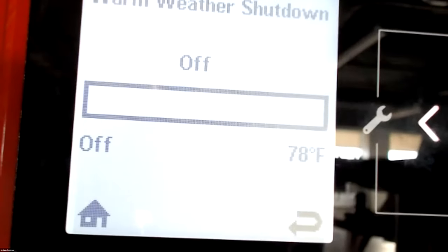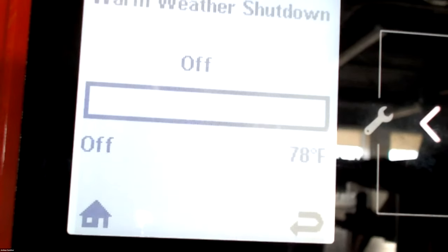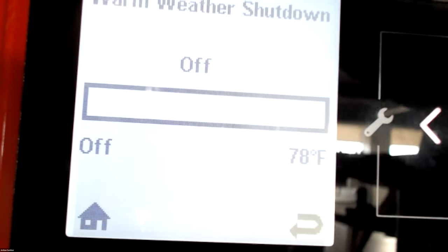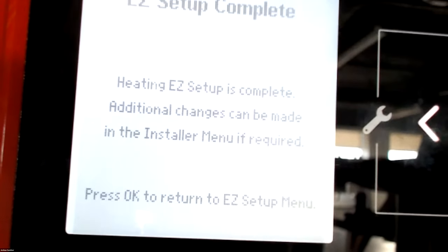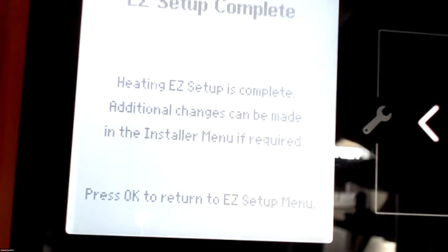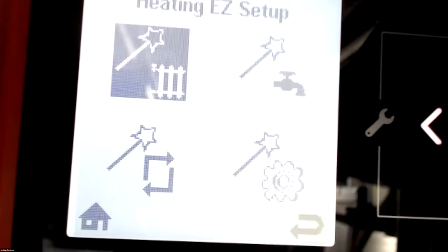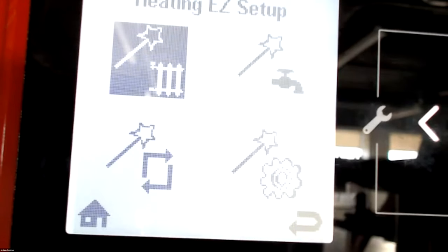You also can see where these temperatures come into play with our outdoor sensor placement. That's why it's critical reading the actual accurate outdoor temperature and we're not being thrown off by exhaust or the sun. The warm weather shutdown, we want that off. We just hit the center circle button. Boom, done. Easy setup complete. Press the OK to go back. And that's the heating easy setup.